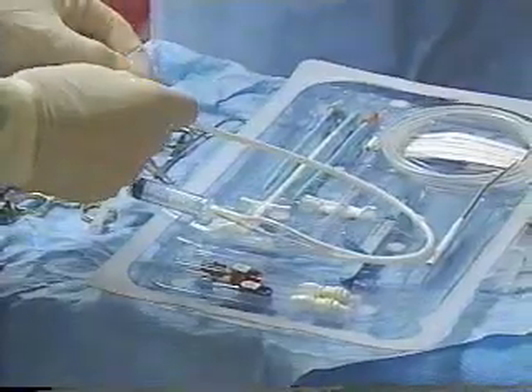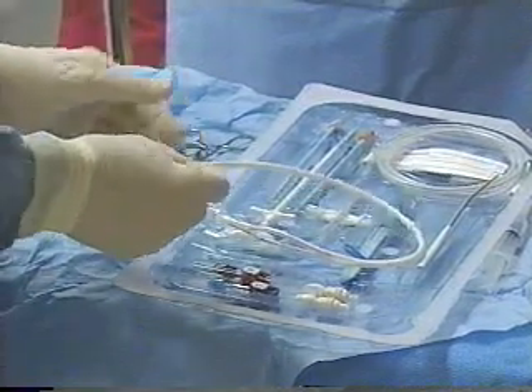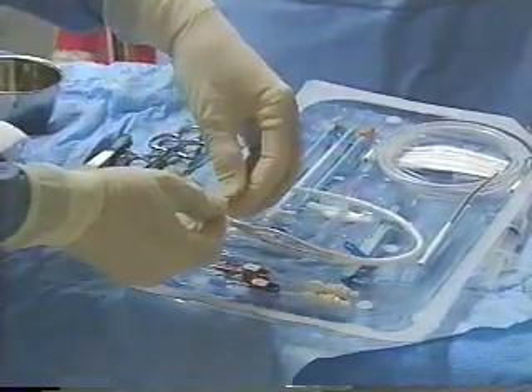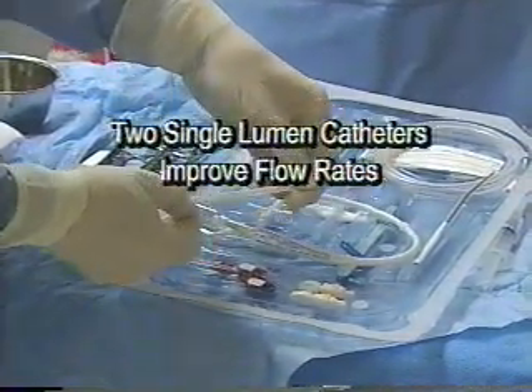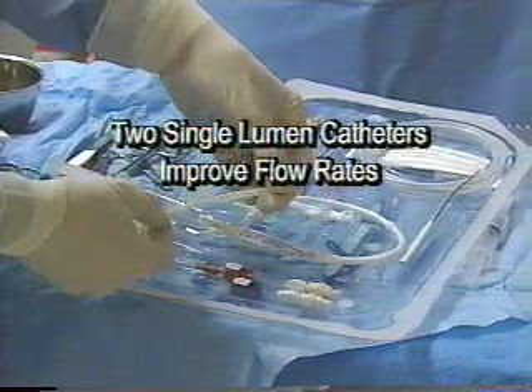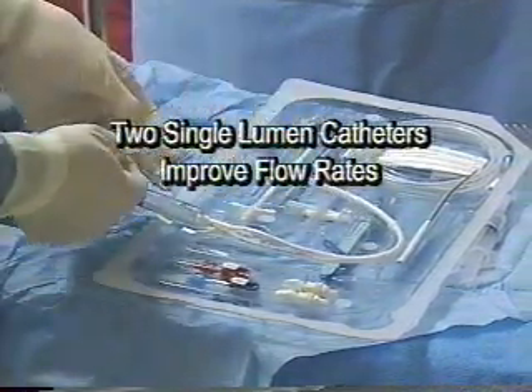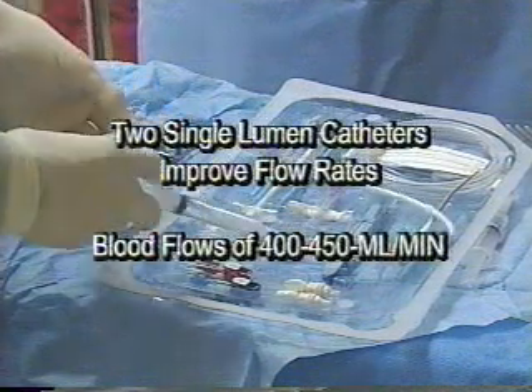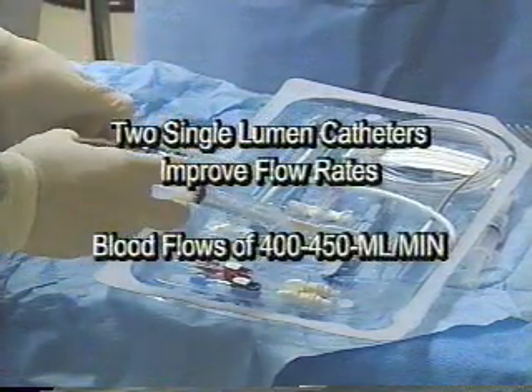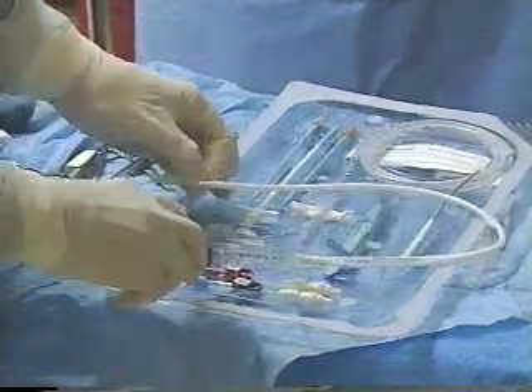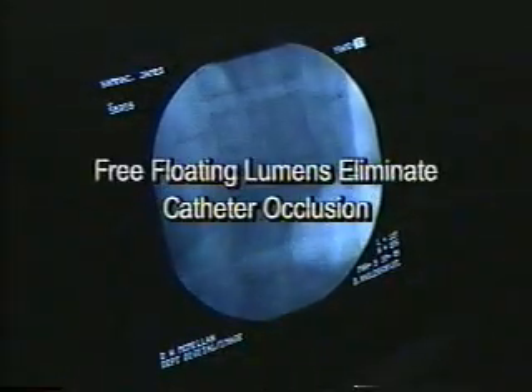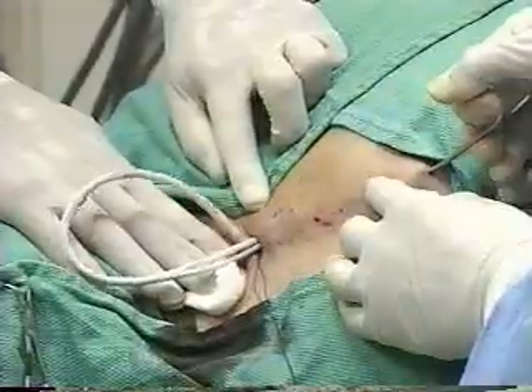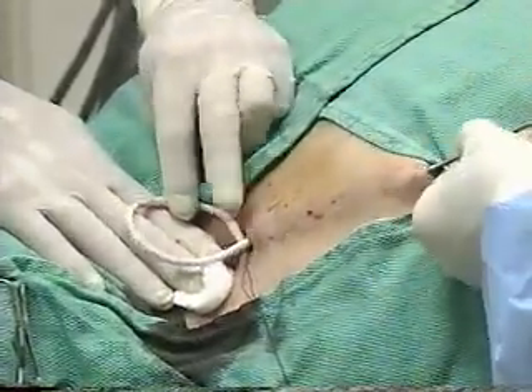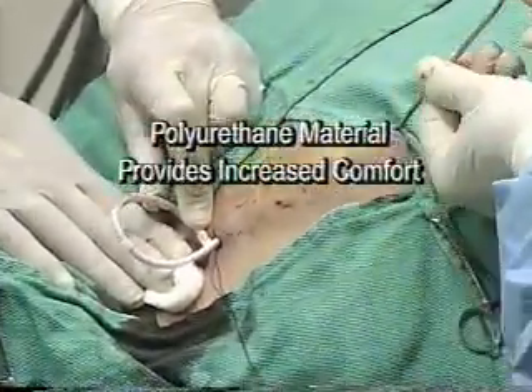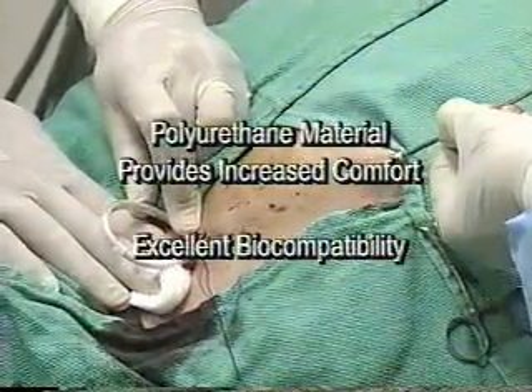The MedComp split stream offers numerous benefits to both the patient and the caregiver. The two single-lumen catheters dramatically improve flow rates compared to traditional plastic or permanent cannulas and allow blood flows of 400 to 450 milliliters per minute with acceptable venous resistance and long-term patency. The two free-floating lumens help eliminate catheter occlusion by the vein. The split stream is manufactured from soft radio-opaque polyurethane material, which provides increased patient comfort while providing excellent biocompatibility.